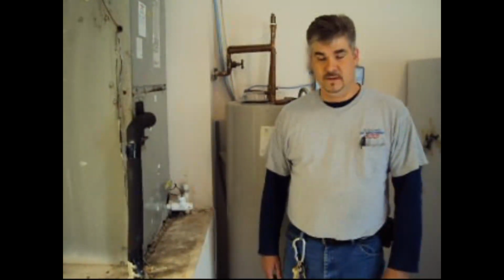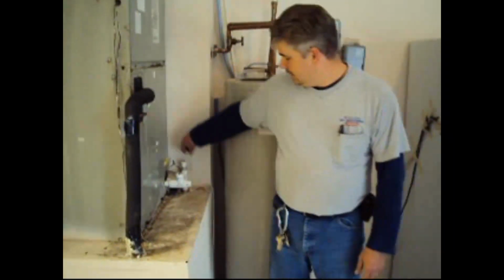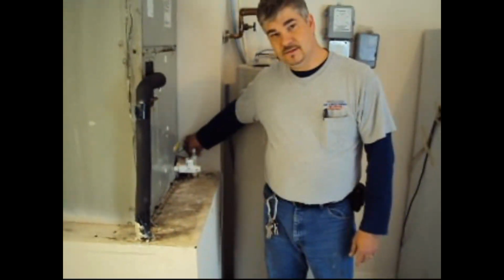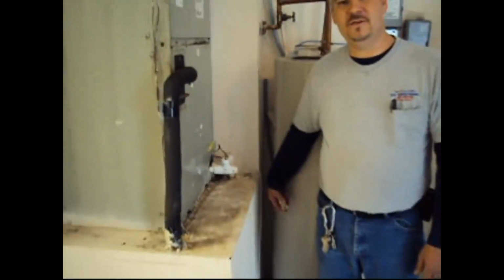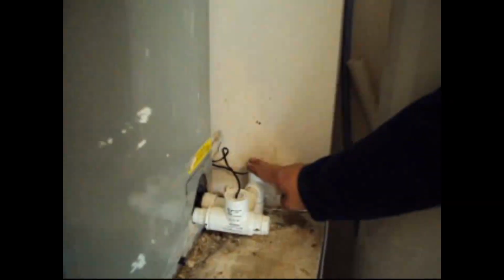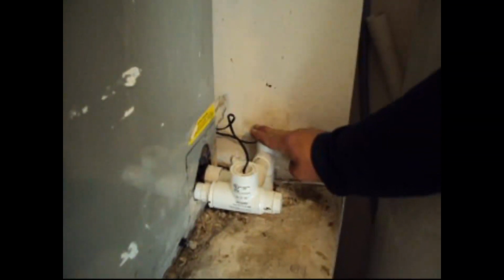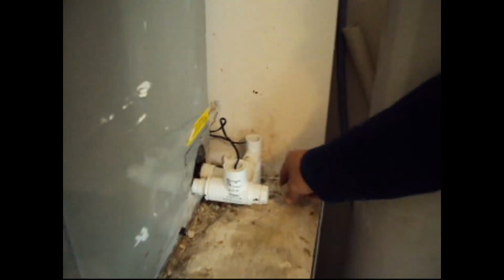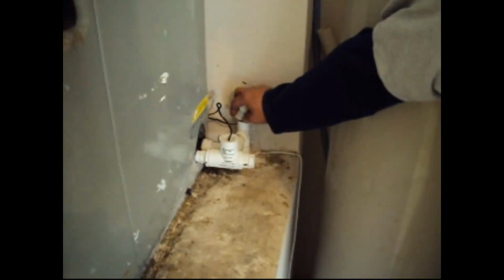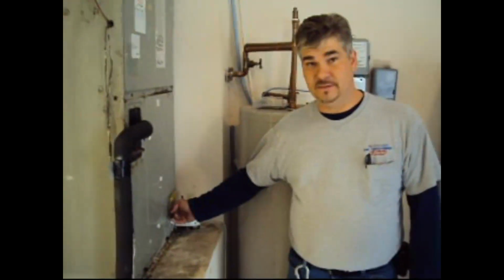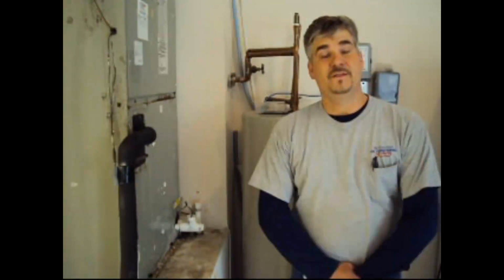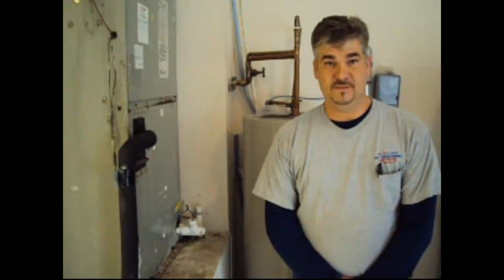So now we've got our vacuum cleaner sucking on the drain line outside, and we want to verify that our drain is clear. So we've left it running, and all you have to do is come inside to the T, pick up the key, and listen if you hear air moving through it. That means that the shop vac outside has sucked all the water and goo out of the drain line and into the vacuum. If you had a blockage, it will have pulled it out all the way from inside the drain pan. So hopefully this video will save you an unnecessary service call.